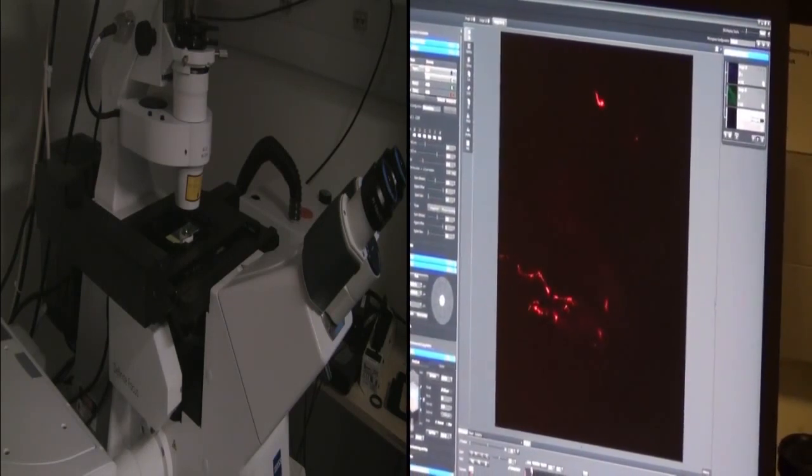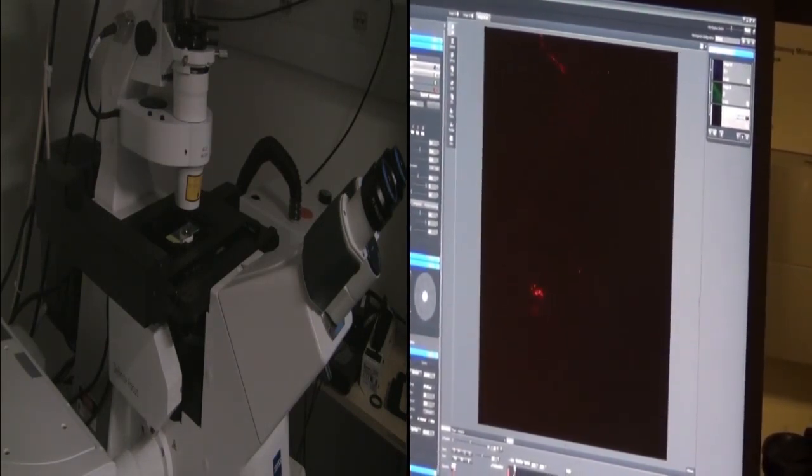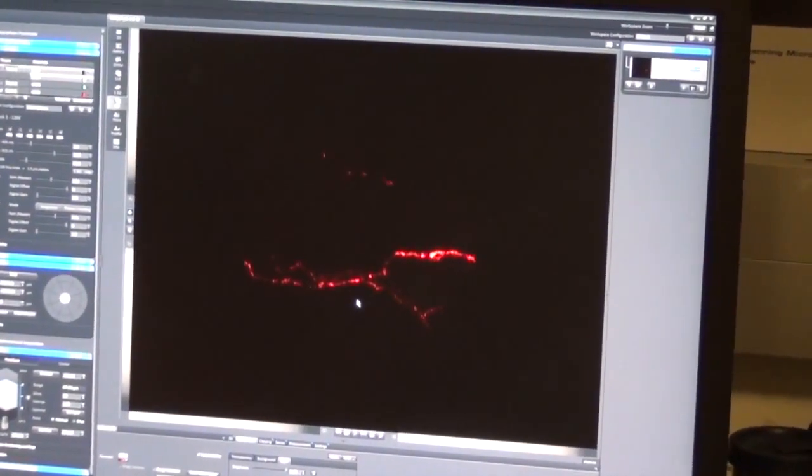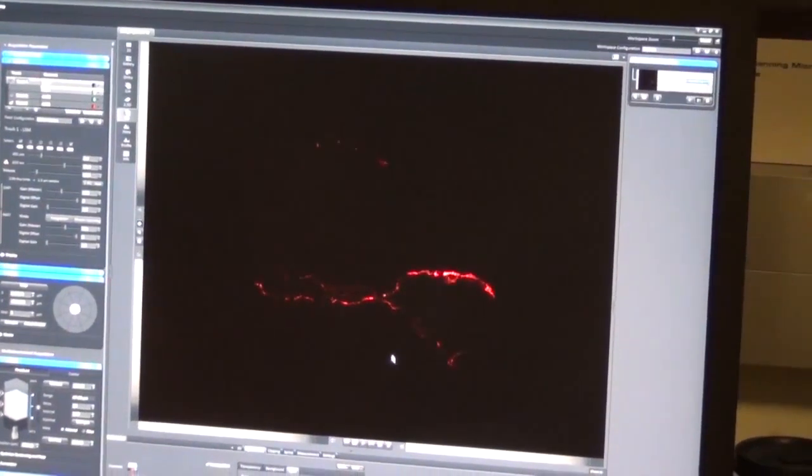This technique of eliminating out-of-focus light is called optical sectioning. There are several different ways of doing this, but the most standard is the laser scanning confocal microscope. In the laser scanning confocal, we acquire an image of just the fluorescence from the focal plane. By slightly adjusting the focal plane relative to the sample, we can create a series of optically sectioned images that we reconstruct into a 3D volume of the sample. However, because images must be acquired point by point, image acquisition is very slow and it can take a very long time to collect a dataset.